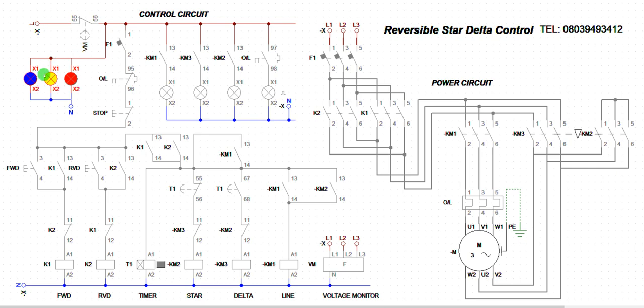I have mains here, mains is active. If we have any phase failure here, there is a protection relay here called voltage monitor that's responsible to disable the function. If one of the phases is not active, this voltage monitor will not allow any voltage or current to flow to this circuit, so the motor will not run.